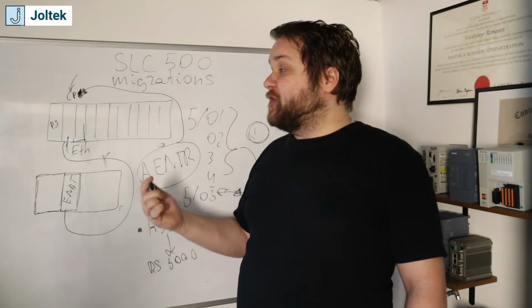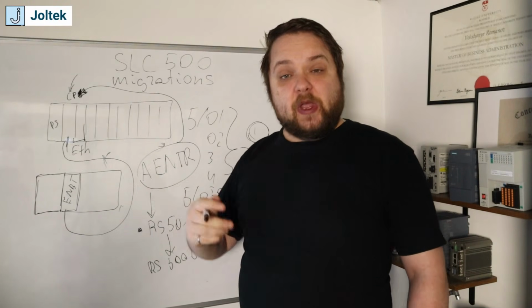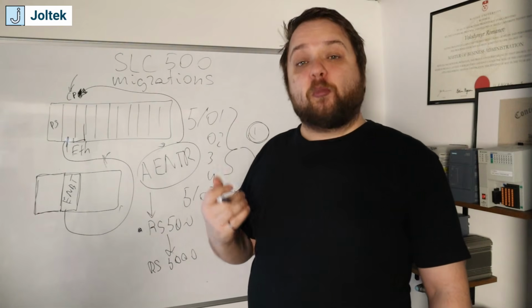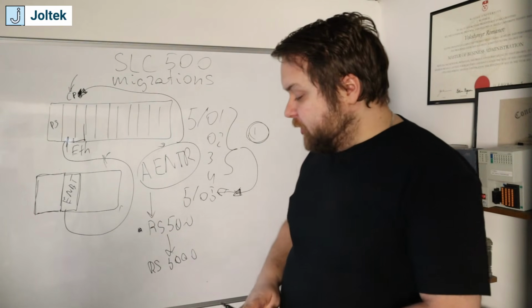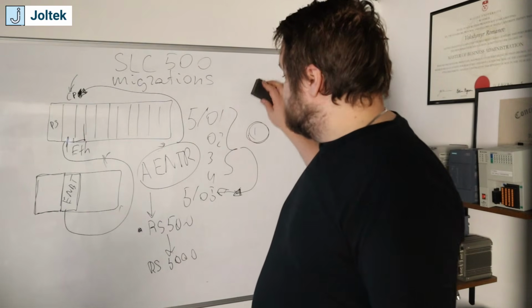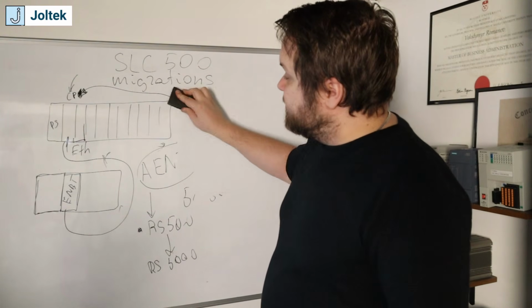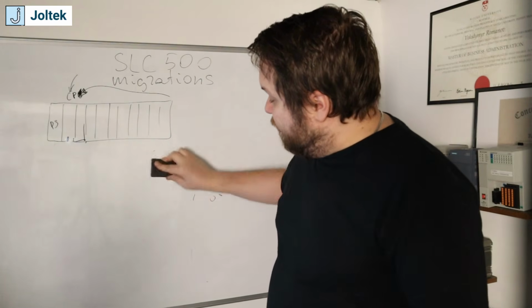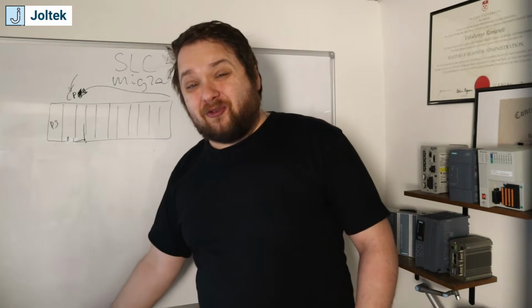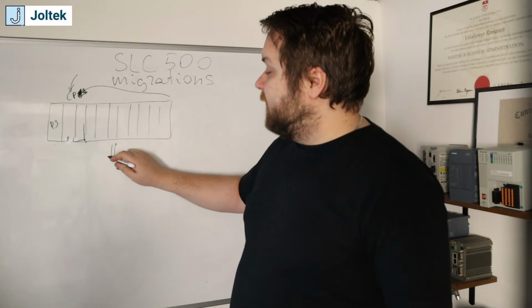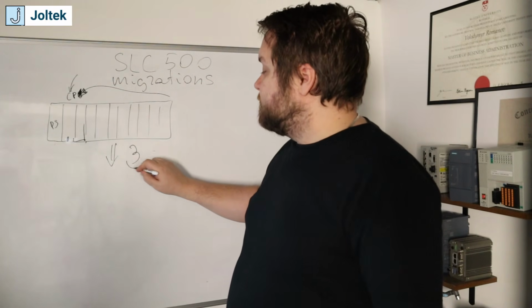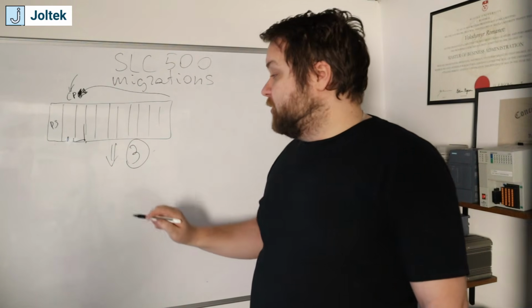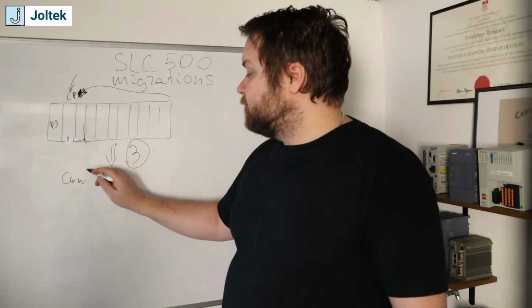Therefore, it's possible that you cannot simply migrate to a quote-unquote remote IO block, and you need to think about a more permanent solution. And so at that point, you have several options, and I'm going to just make space on this whiteboard for a moment. However, at this point, you're migrating the entire rack to an entirely different platform. And this I will call migration scheme number 3.